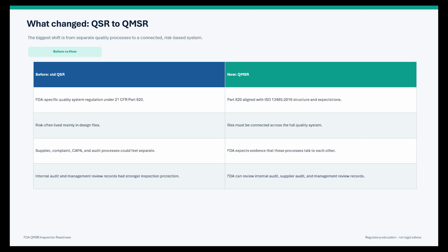Another important change is visibility of certain records. Internal audit records, supplier audit records, and management review records previously had stronger inspection protection. Under QMSR, companies should be prepared for the possibility that FDA may review these records during an inspection. So the main point for this slide is that QMSR is not just a paperwork update. It is a system behavior update.